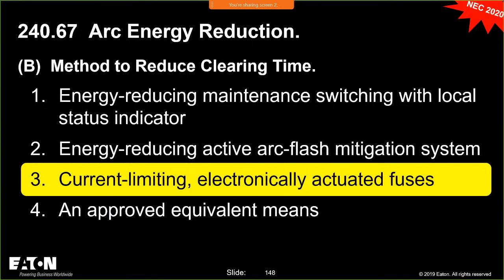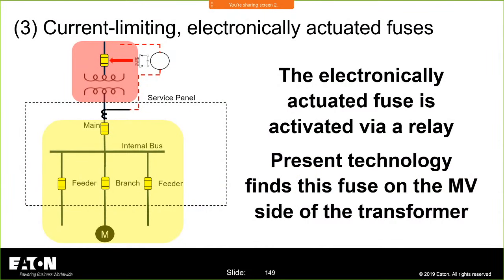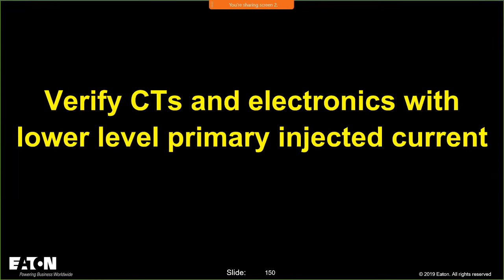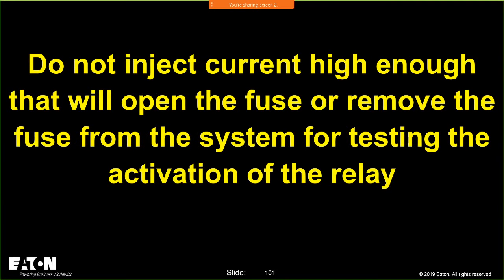You need a complete record of your testing. The electronically actuated fuse, again, is activated via relay. There are ways to test everything other than telling that fuse to open, right? You're going to verify the CTs with low current injection. You're not going to inject high current that tells that fuse to open, all that good stuff. Again, you're going to just make sure that everything that's technically working should work, right?